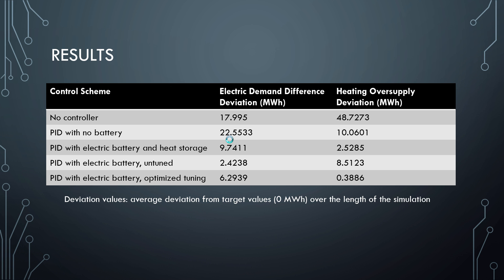We started with the base value for both our electric and heating oversupply. In order to be advantageous, the system had to have lower deviation values than those baselines. This is a couple of the systems we tried that seemed somewhat feasible — there were others that weren't as robust. For example, we used a PID controller but removed the battery to see what kind of result we'd get.